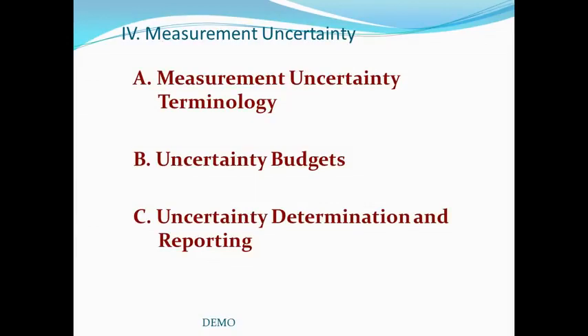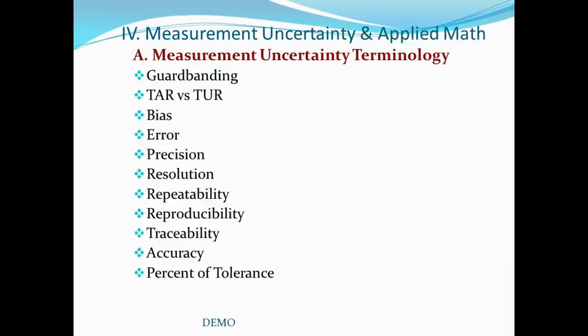Let's expand this outline. Some of the terms included with measurement uncertainty are guard banding, TAR, which is test accuracy ratio, and TUR, test uncertainty ratio, bias, error, precision, resolution, repeatability, reproducibility, traceability, accuracy, and the percent of tolerance.